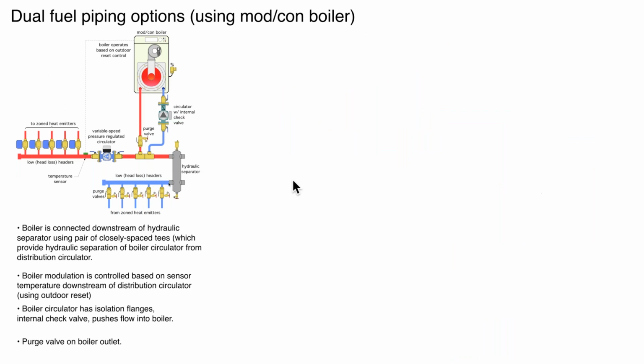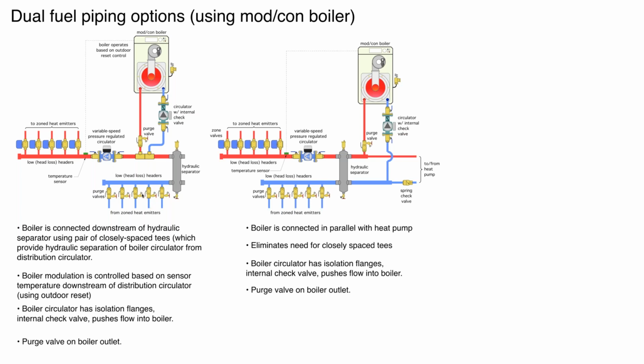There are different ways to connect the boiler in. Here's one way. This is with a set of closely spaced T's. It's connected downstream of the hydraulic separator. Again, to the left, you've got the variable speed pump and the zone valves, and these are just the returns. This shows it connected in parallel. This would be on the upstream side of the hydraulic separator.